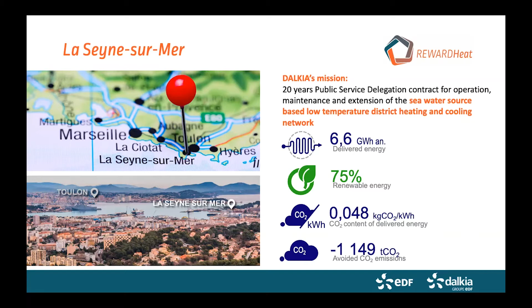So just about the network itself. You have 3 main blocks. First, the seawater loop, with a pumping station and exchange station that draws and injects seawater from the port area at about 4 meters depth. This ensures the seawater stays in a closed cycle and doesn't interfere with the primary network, which is the second block, the low temperature loop, filled with clean water so there's no corrosion issue with the piping. It operates depending on the sea temperature, which varies between about 12 and 25 degrees during the year.